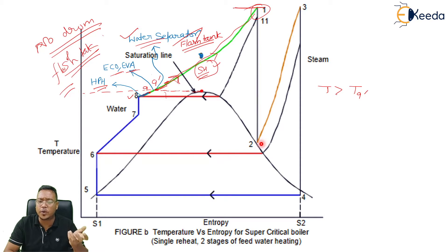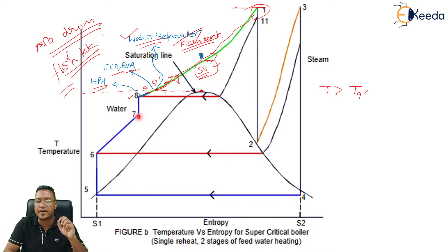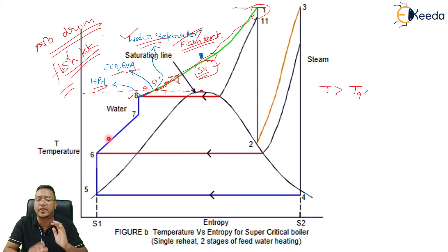From one to two is the HP turbine, two to three is the reheater, three to four is the LP turbine, four to five is the condenser, five to six is the CEP, six to seven is the LP heater, seven to eight is the BFP. By this way, the cycle will complete.